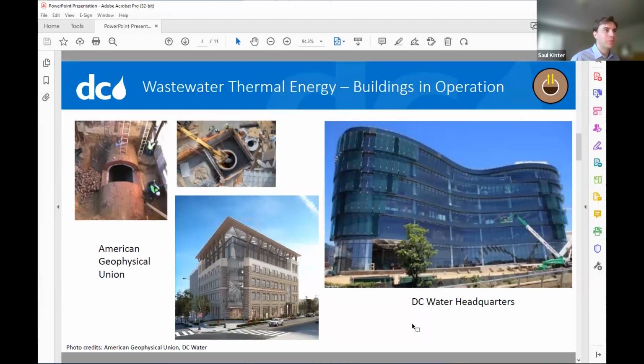We were able to make that connection to the main wastewater flow going through the pump station underneath the building. Much simpler from a civil standpoint than at the American Geophysical Union. We didn't have to dig or cut open a sewer; we just took a side stream off an already existing pipe and connected it to a heat exchanger.